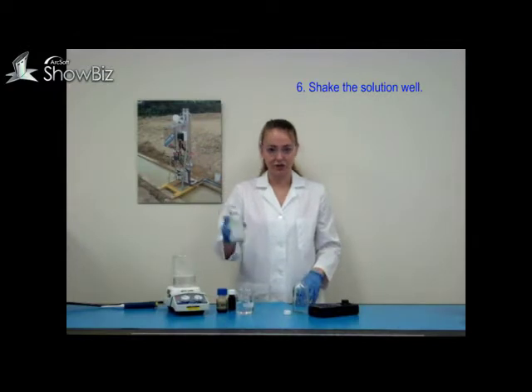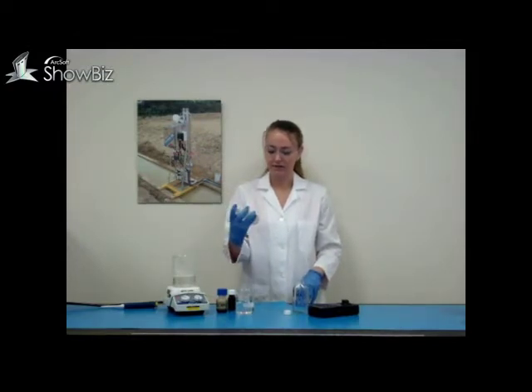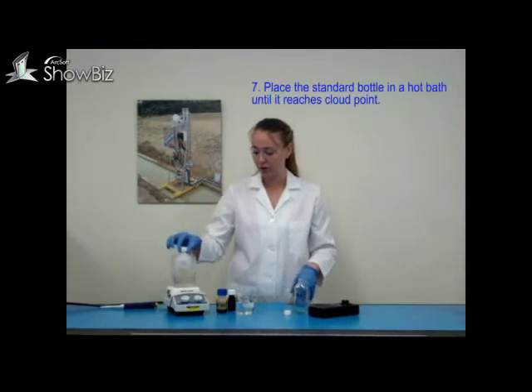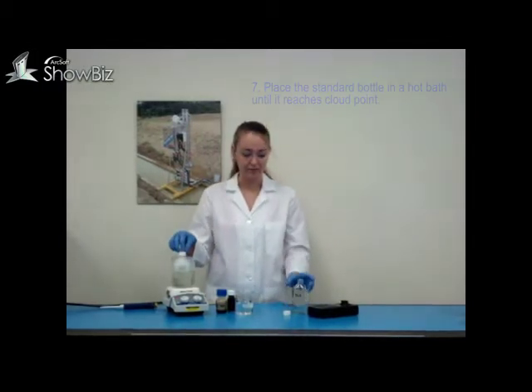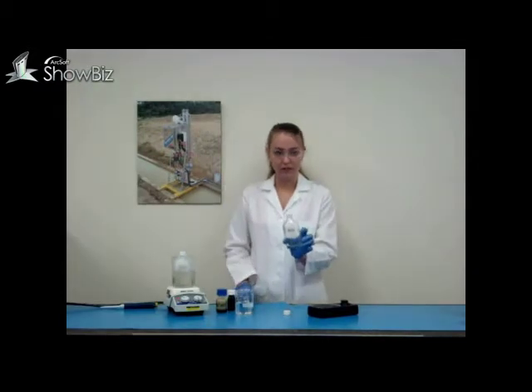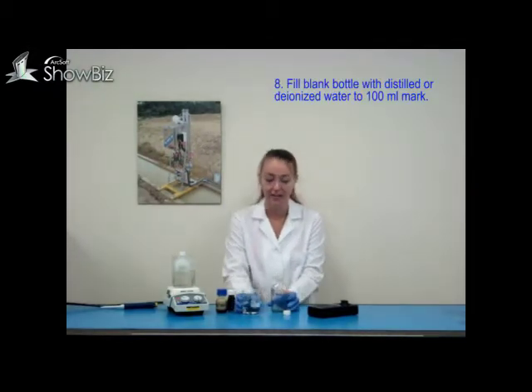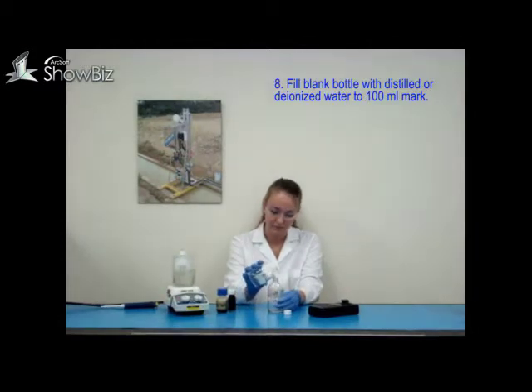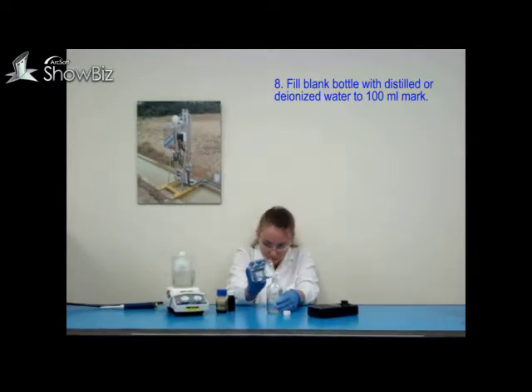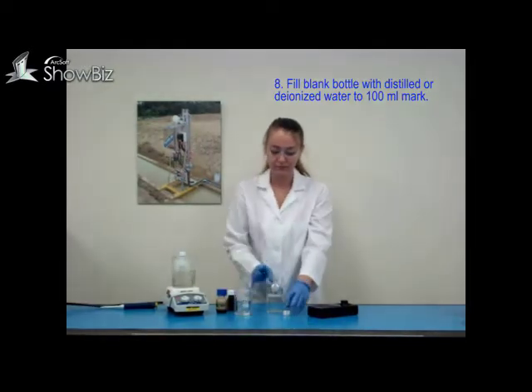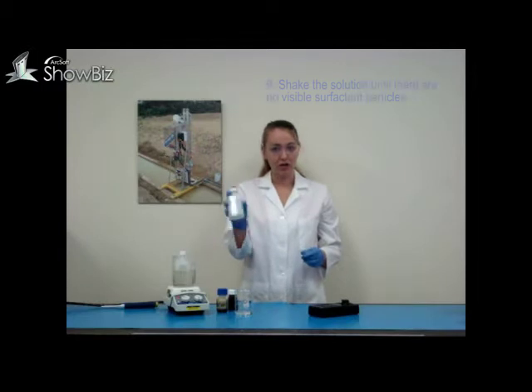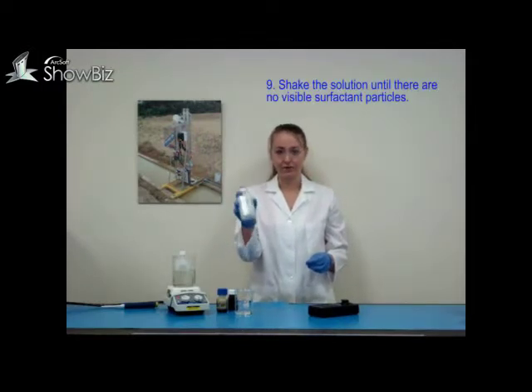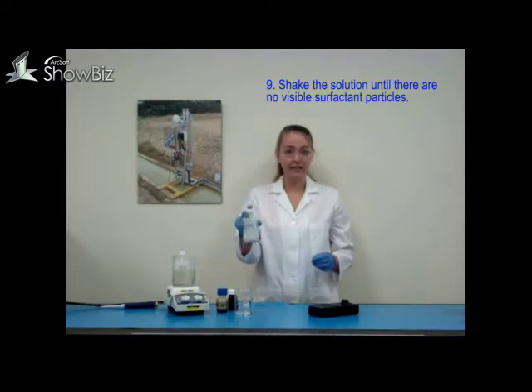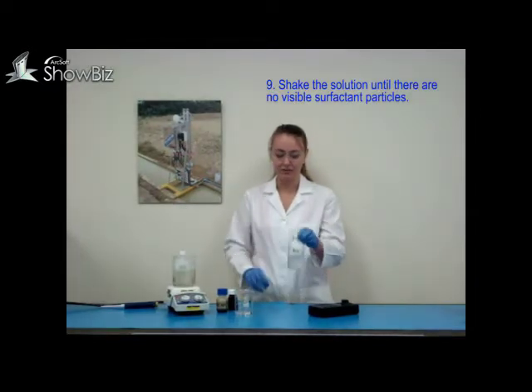Cap the bottle and give it a good shake. Then place your standard solution in a hot water bath so that the solution may reach cloud point. For your blank, you also need to fill to 100 milliliters with either distilled or deionized water. Cap and shake your blank solution until you can no longer see any particles of surfactant floating in the solution. Once you have completed that, you have made your blank calibration solution.